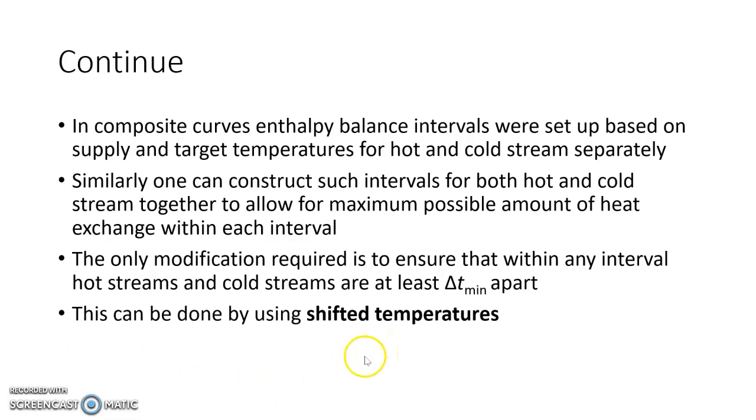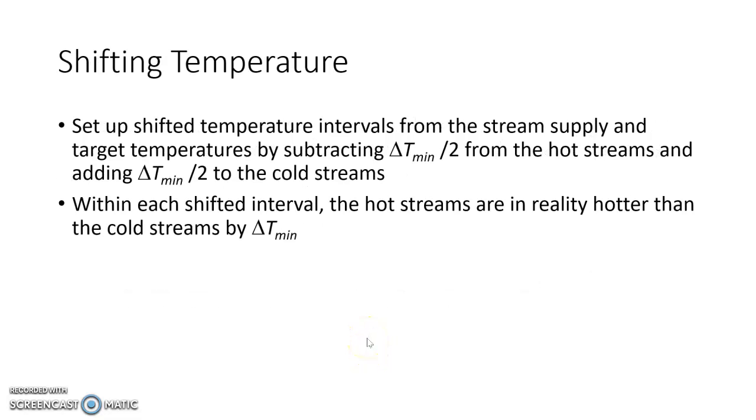We say that delta T minimum is 10 and accordingly we decide our further course of action. So we need to make a shifting of the temperature. How do we shift the temperature? For shifting the temperature, we have to do delta T minimum by 2, subtract it from the supply and target temperature from hot stream making them colder, and add delta T minimum by 2 to cold stream making them hotter. So for every interval, the shifted temperature will make sure that hot streams are really hotter than the cold stream by minimum delta T. So within each shifted interval, the hot streams are in reality hotter than the cold stream by delta T minimum.